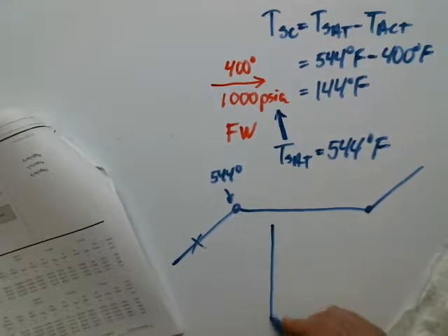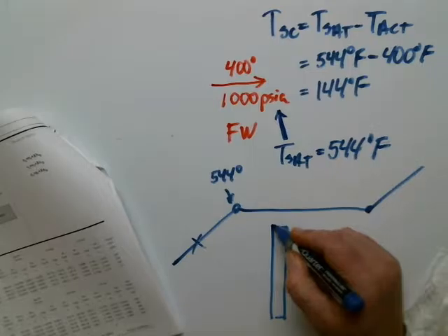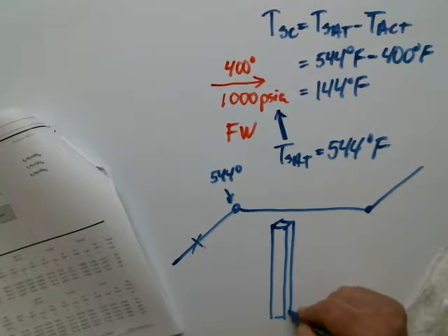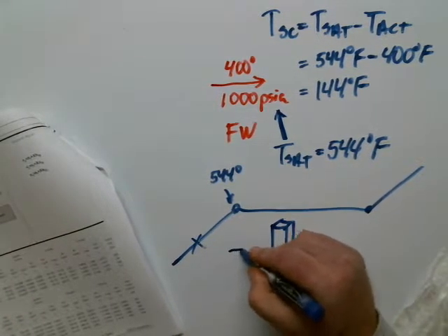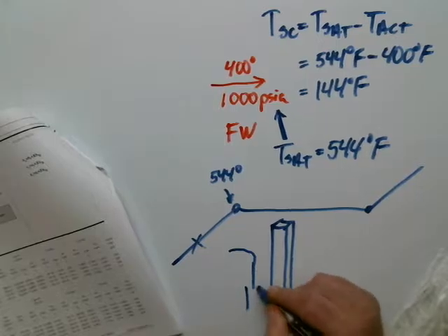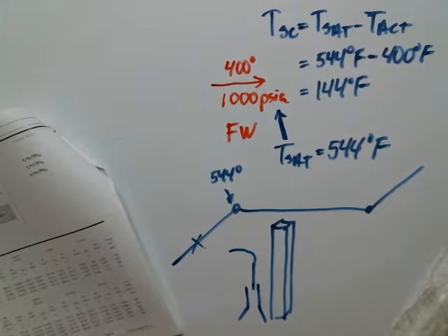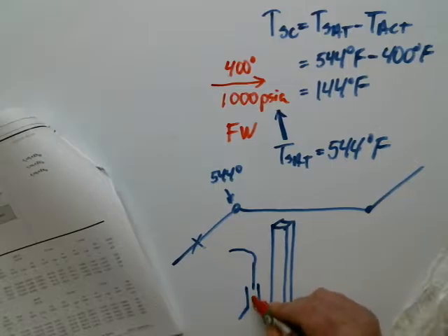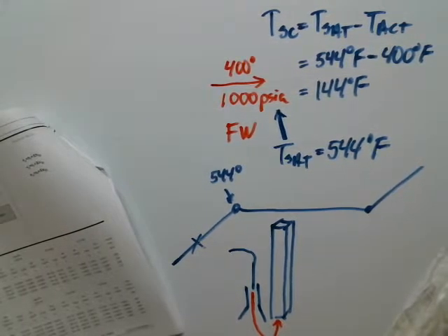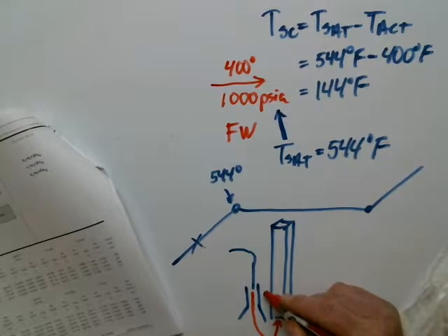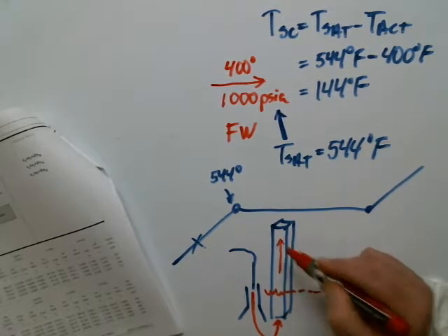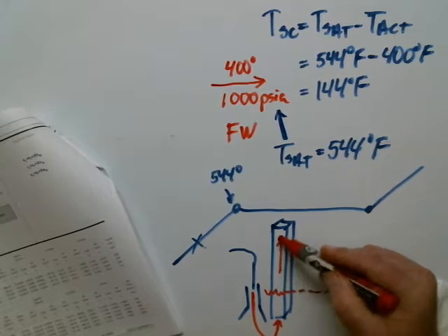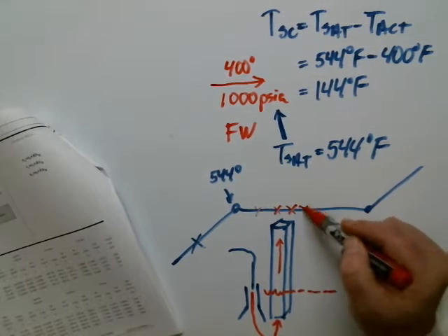Little look ahead here. Here's a fuel bundle. So water enters subcooled into the reactor. We know that it gets preheated in the downcomer and ends up going through jet pumps. Gets a little warmer and preheated. Enters the bottom of a fuel bundle, subcooled. At some point, boiling starts to occur. This is where saturation occurred in a fuel bundle, and this is nothing but an increase in enthalpy as it travels across the fuel bundle.